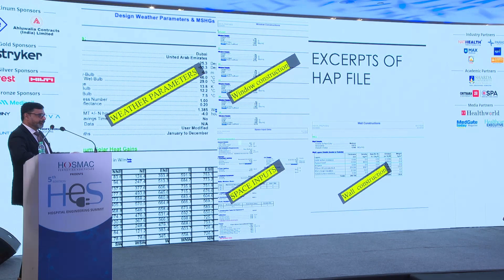As I said, the HAP calculations will have the weather parameters of the place, the window construction, the wall construction, and the space inputs. All this incorporated, we get to know the total tonnage, and also how much air conditioning is required in every individual room. This helps the HVAC designer decide how to distribute air handling units, whether to have one unit covering a complete zone or to separate the zones. All this becomes possible by doing this kind of calculation.